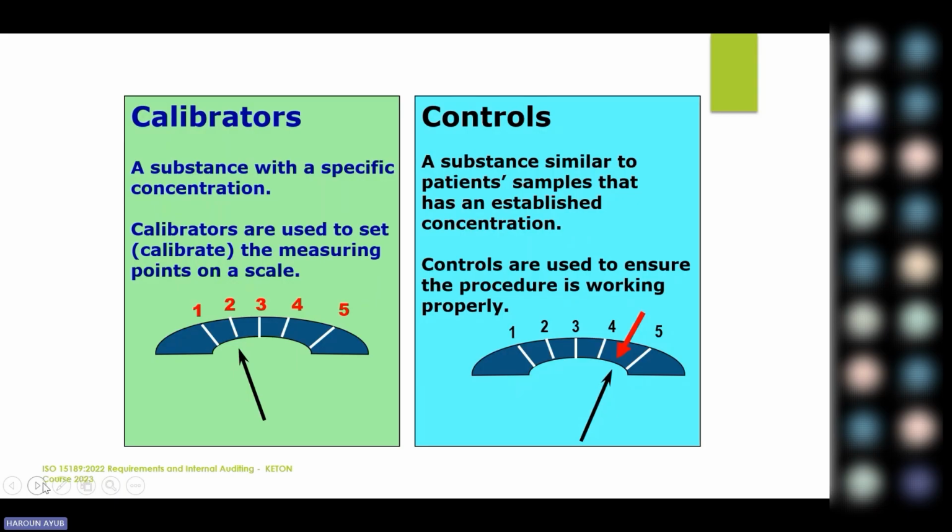So whatever you are getting from the control in your analyzer is an absorbance or an RLU if you're using CLIA systems, or an absorbance value if you're using ELISA systems. So that value will now be put in that particular calibration curve that you have, and then it will give you a value. So if our calibrator is wrong, then your controls will fail.